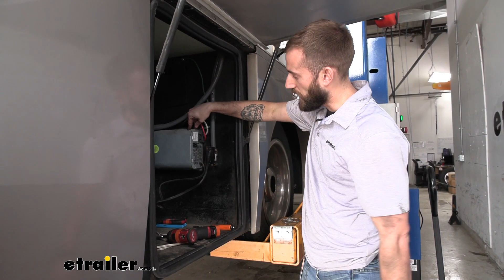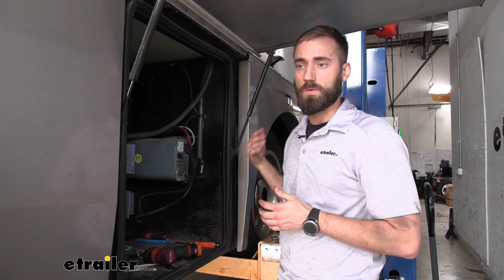So with our one today, it's going to have a 100 amp converter, and on this one it's only a 75. So we do need to check our wiring, make sure that everything's going to be a thick enough gauge so that we can properly transfer that power without it burning out the wires or popping any circuits. Along with that, we also have our AC side.